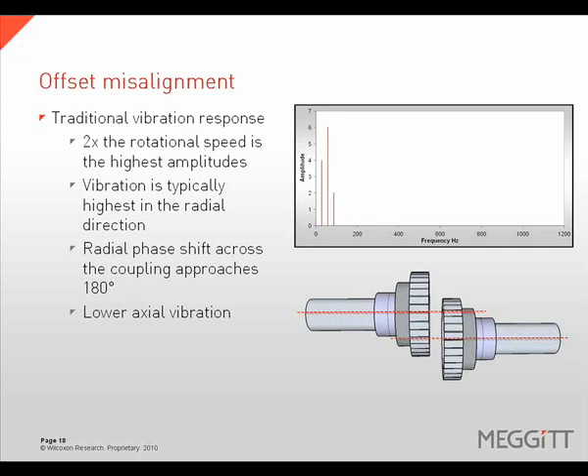Offset misalignment is traditionally characterized with a 180 degree phase shift across the coupling in the radial direction. It is important to look at the machine as a whole and not just the readings across the coupling. Pure offset misalignment will typically exhibit lower axial readings when compared to the radial readings.